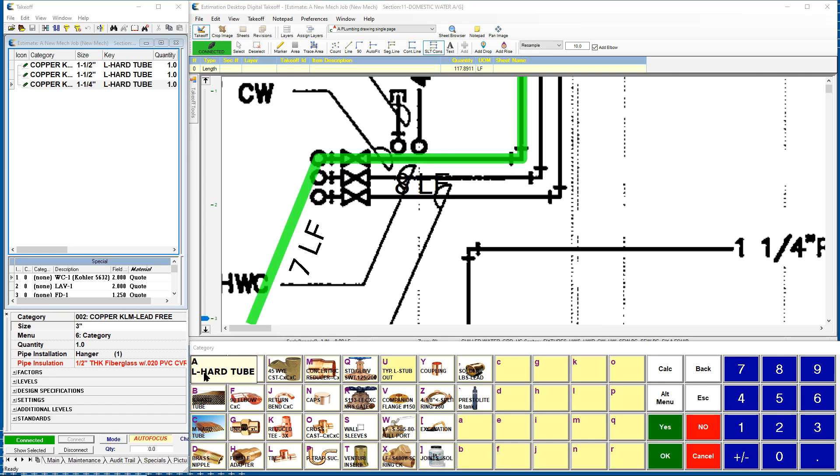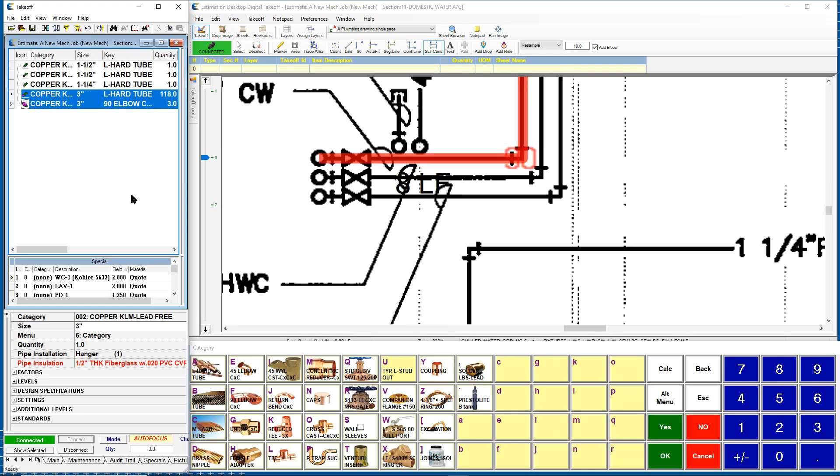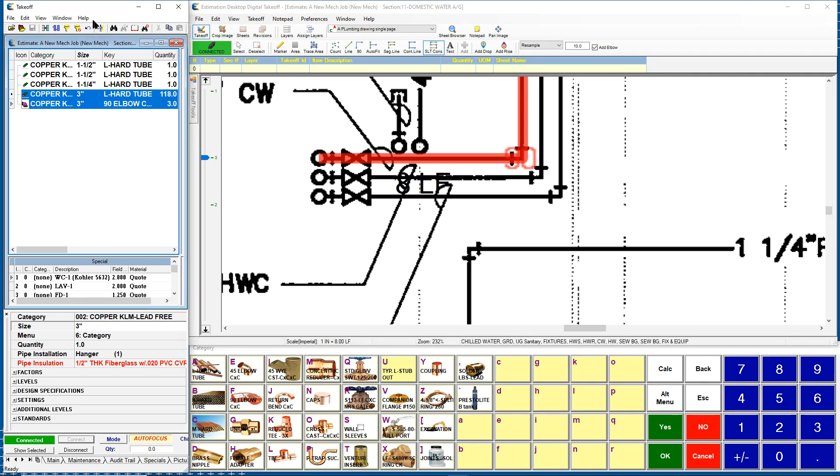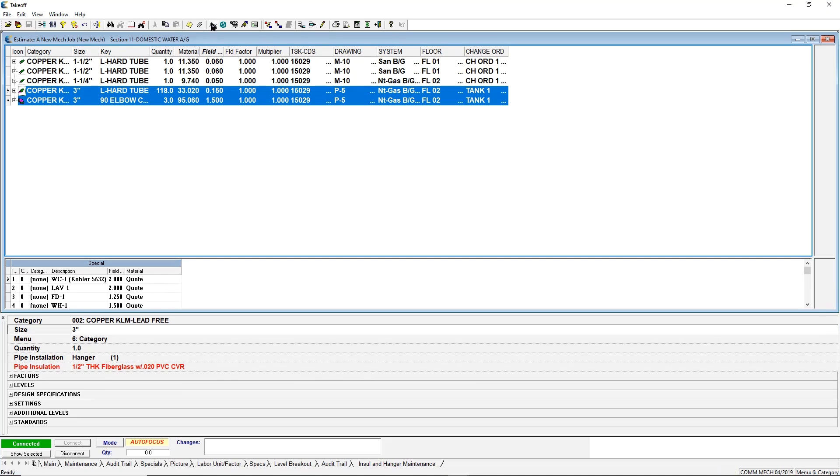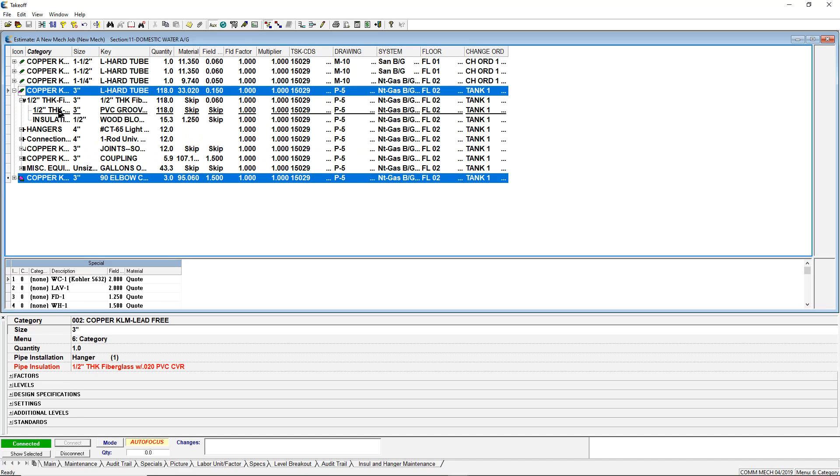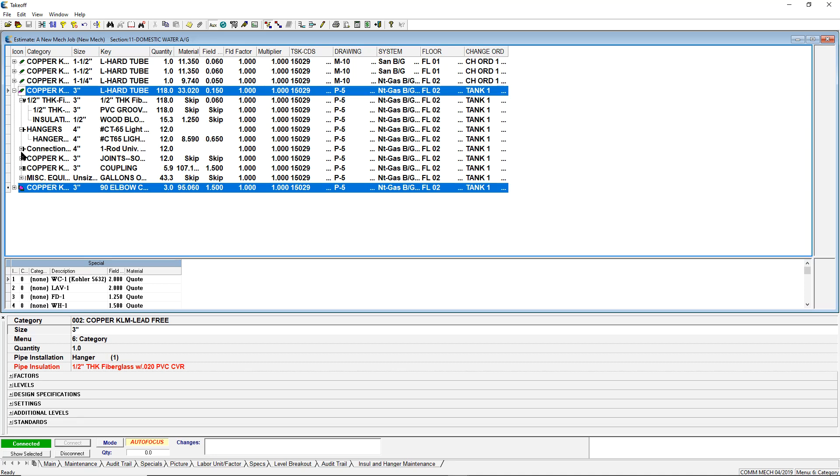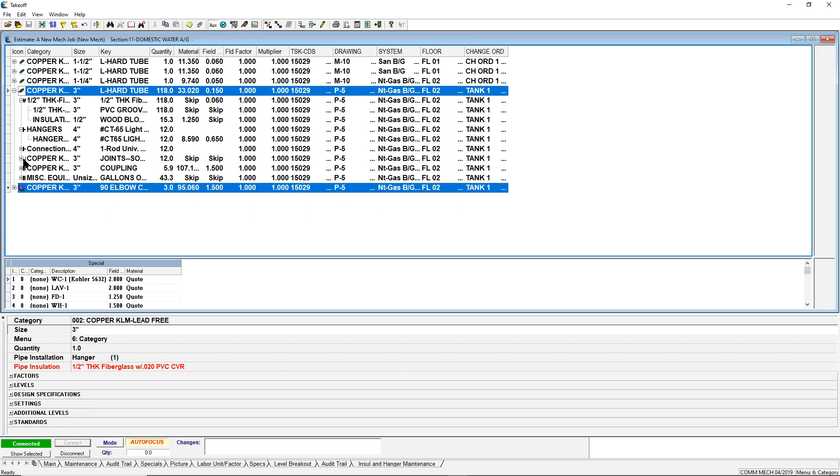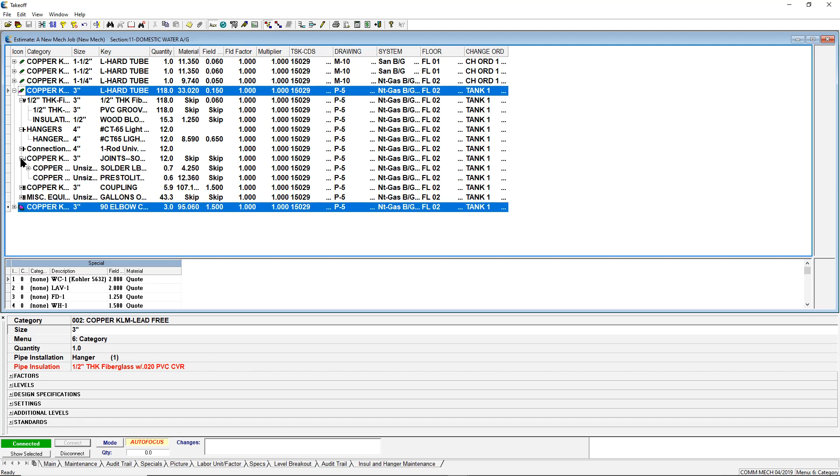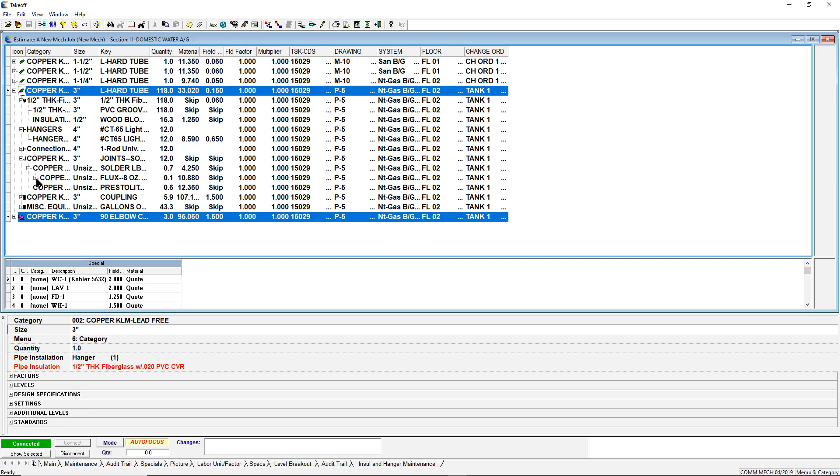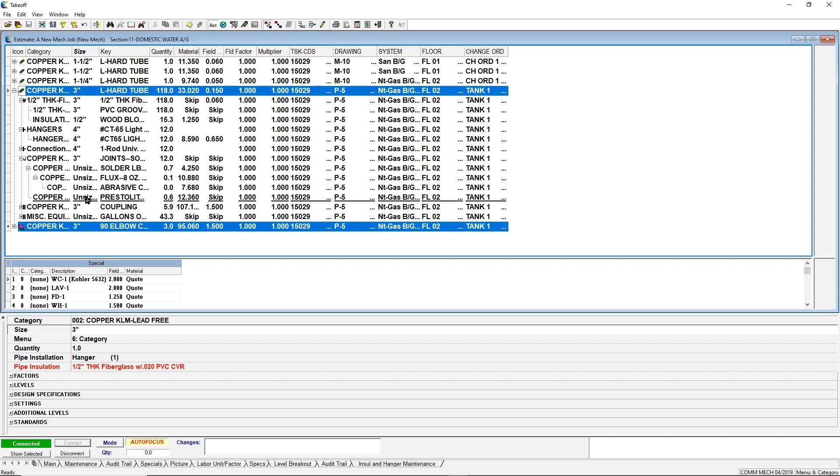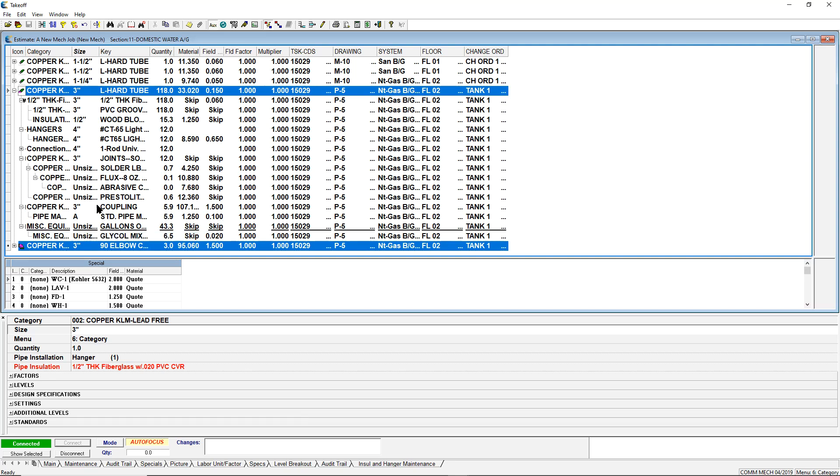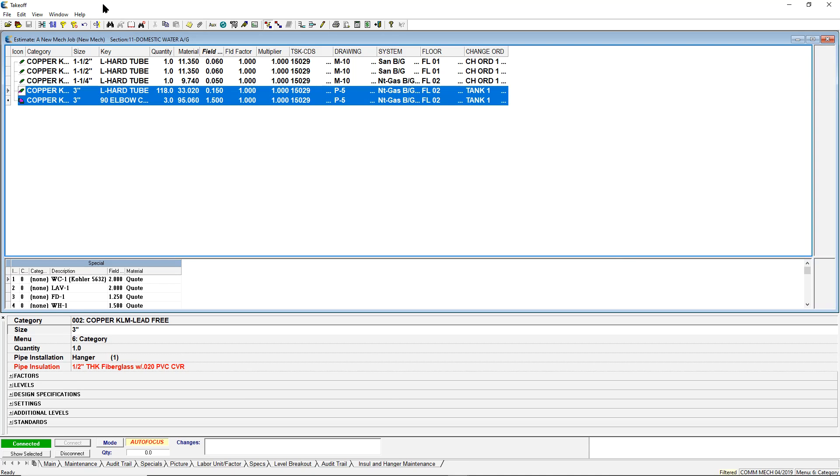As I'm doing this, it's measuring out the appropriate quantities of pipe that I require, and also picking up any in-line fittings like 90s or 45s for me automatically. You'll notice it gave me the 118-foot run of pipe, but it's also picked up those three in-line fittings and marked it up on the plan. It's not just giving you pipe and fittings. It's given me the quantities of insulation I require, my clevis, beam clamp, all-thread, all the parts and pieces for those hangers, all of my byproducts like solder, flux, and abrasive cloth, couplings, pipe markers, and even the gallons of water and glycol mix.